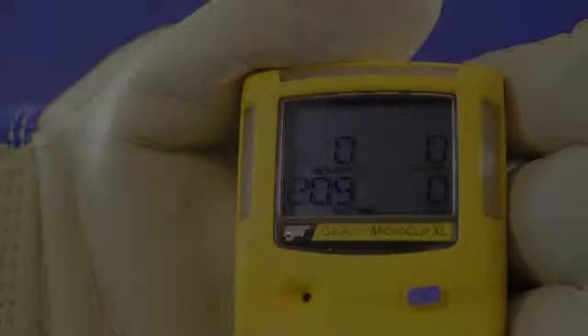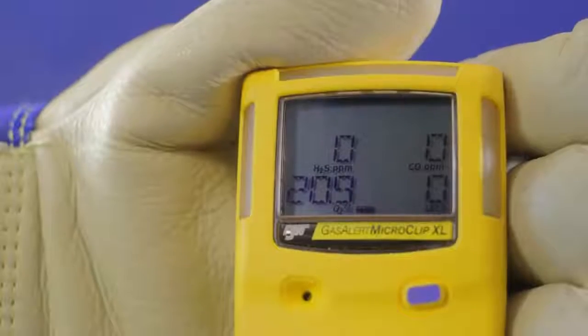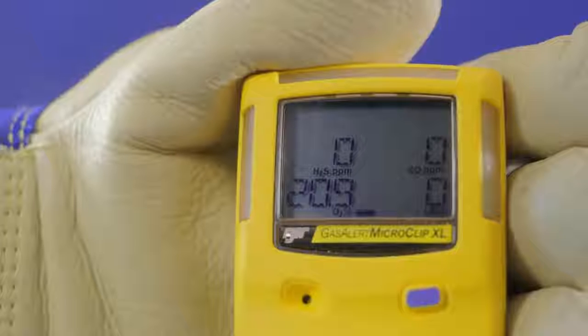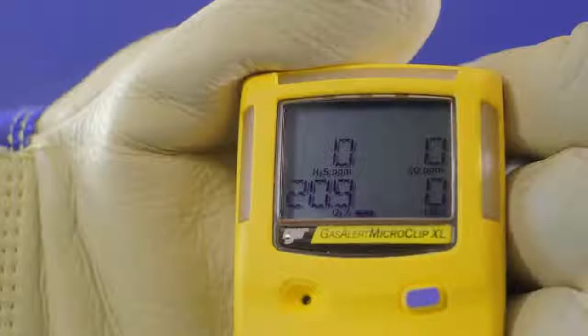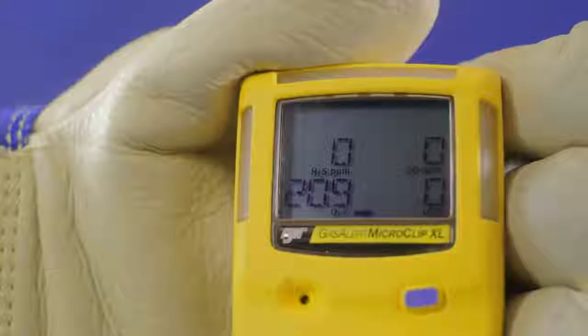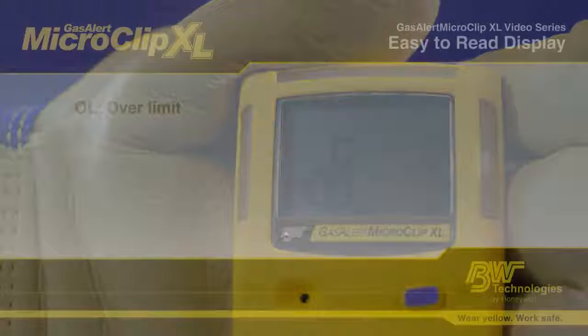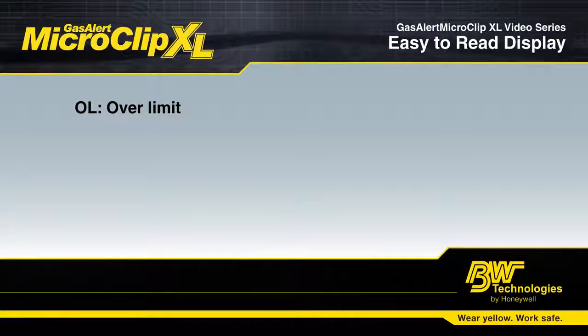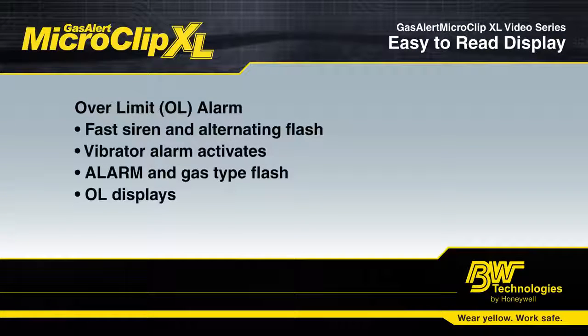If you are taking proper action and evacuating any time a low or high alarm is sounded, your Gas Alert Micro Clip XL should not go into STEL or TWA alarm. The fifth type of alarm is an OL, or Over Limit Alarm. This means that the level of gas in the environment is beyond what the sensor can measure. OL will flash in place of the reading of that sensor.